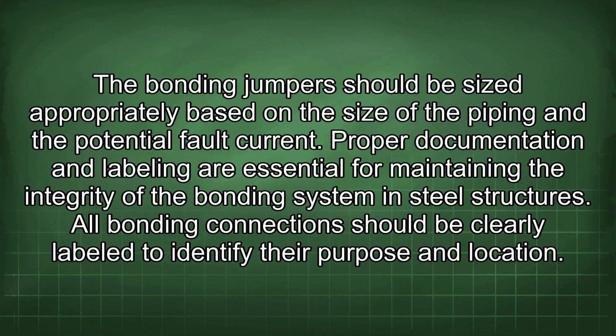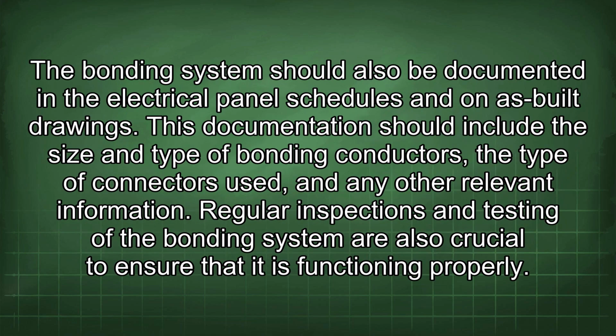Proper documentation and labeling are essential for maintaining the integrity of the bonding system in steel structures. All bonding connections should be clearly labeled to identify their purpose and location. The bonding system should also be documented in the electrical panel schedules and on as-built drawings. This documentation should include the size and type of bonding conductors, the type of connectors used, and any other relevant information.